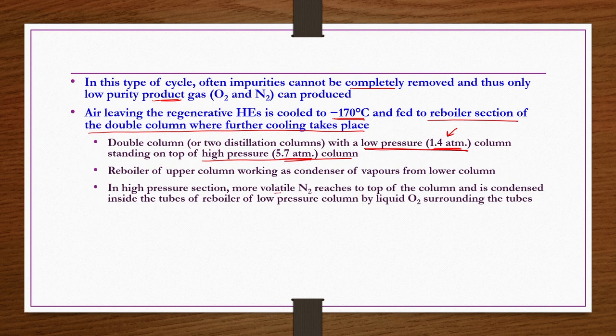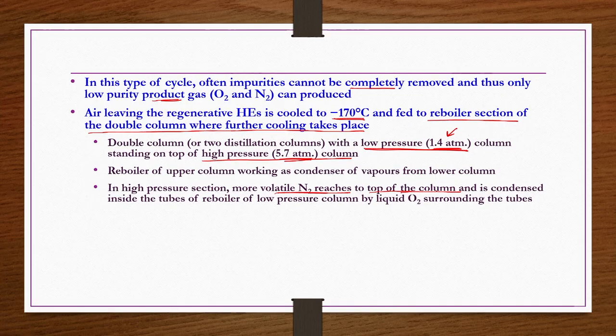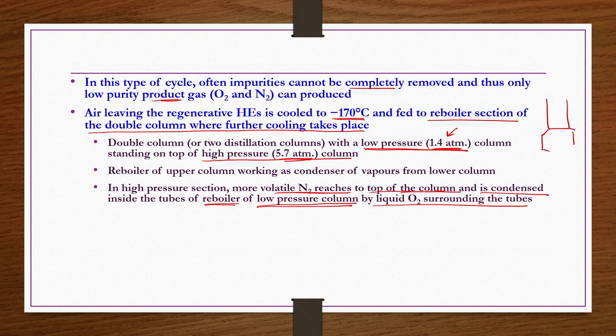In the high pressure section, N2 is more volatile than O2, so it reaches the top of the column easily and is condensed inside the tubes of the reboiler of the low pressure column by liquid O2 surrounding the tubes. The low pressure column is mounted on top, the high pressure column is below, with a heat exchanger between them. The columns are provided with trays — the number of stages required for distillation is calculated from mass transfer principles.